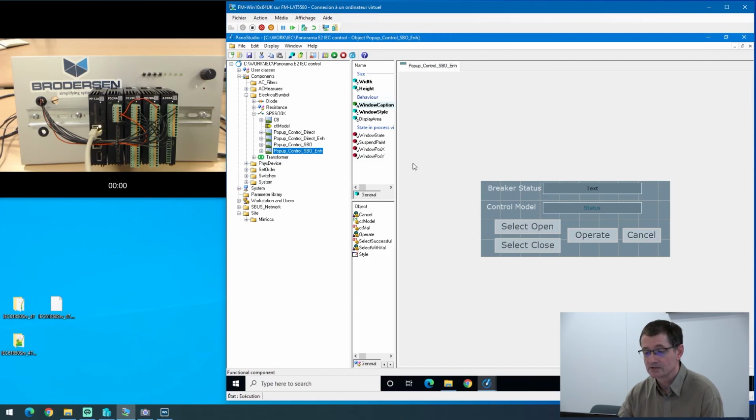The date quality also tells you if the RTU has any issue with time synchronization, for instance. And because it's the quality of the value, it means that even if it happens the day before, when you analyze some alarms or some trends, the quality will tell you if at that time the timestamp was accurate or not. So that's a very big benefit to have it in the quality of the tag and not just as a side information.